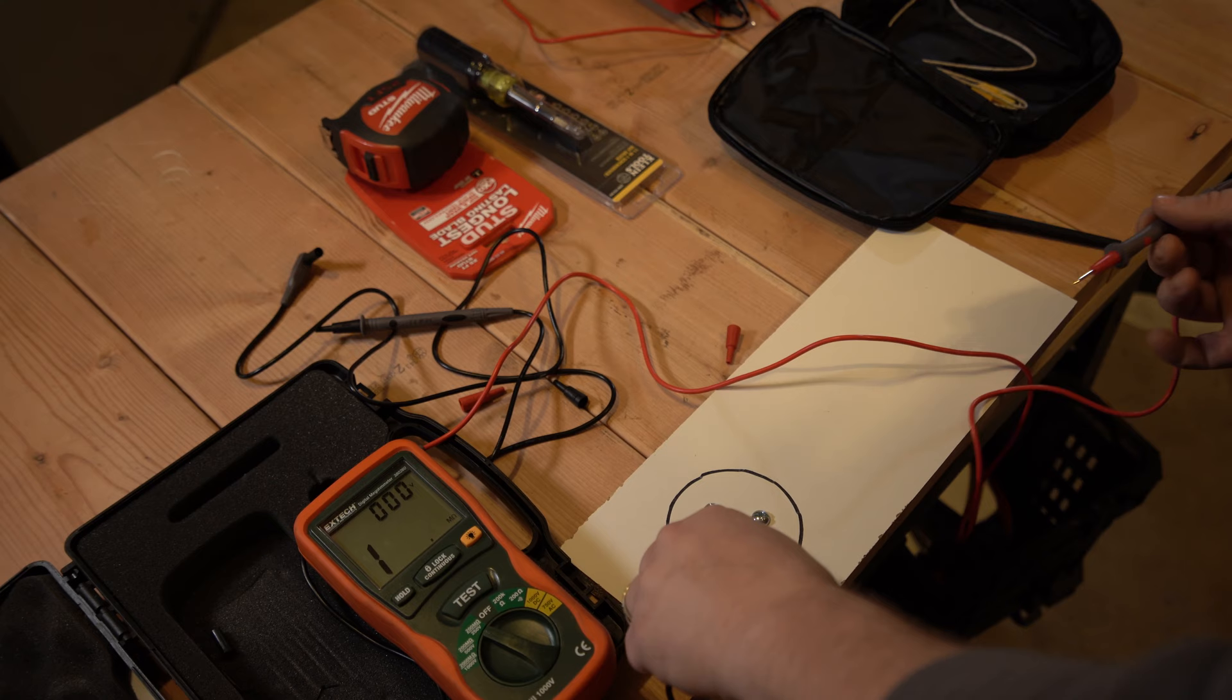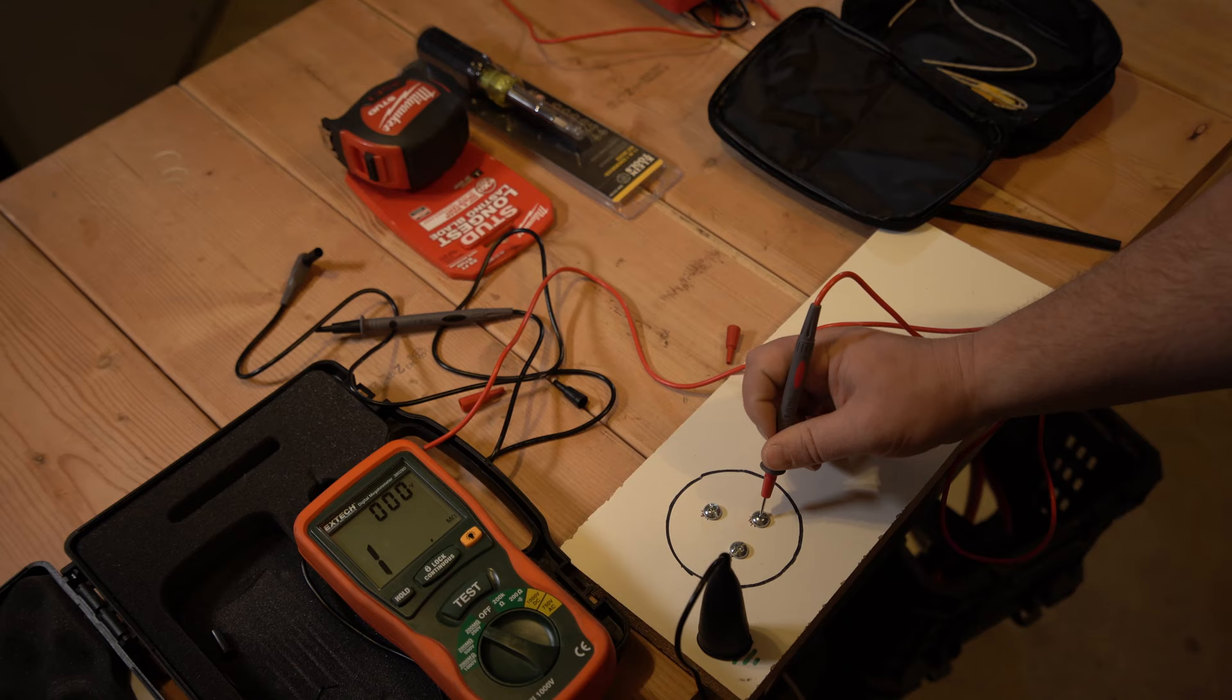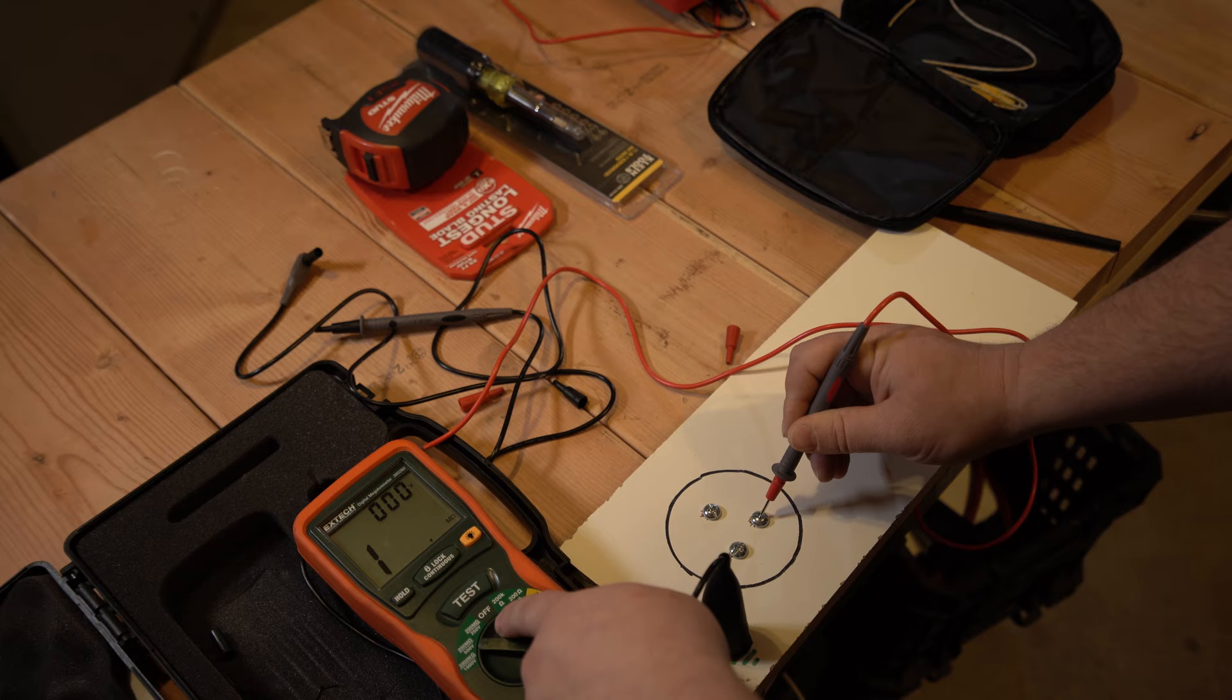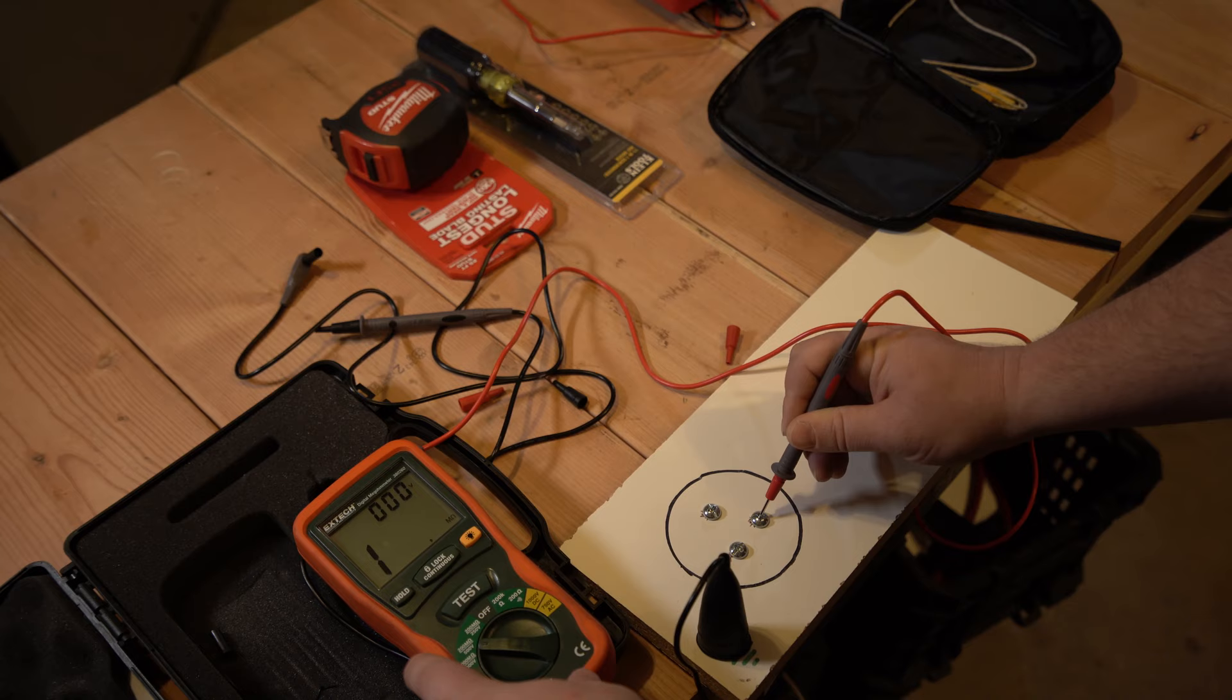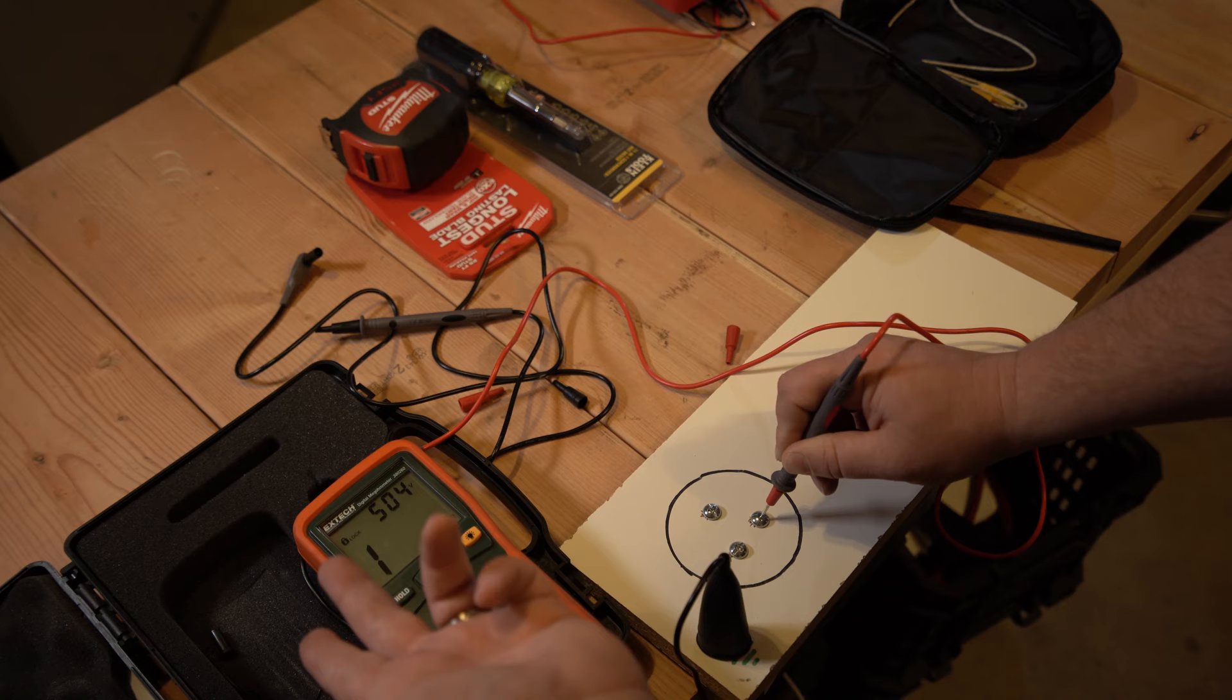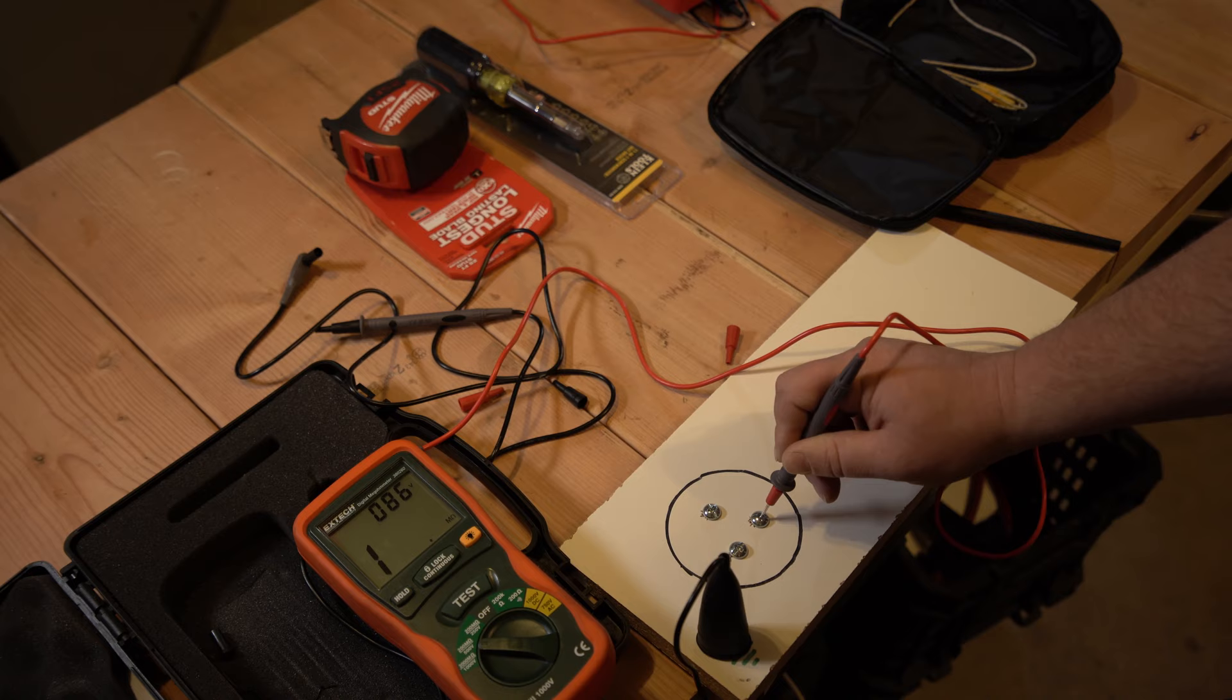After you verify that your meter runs properly, like I said, connect that to a good ground on the housing of the motor or the compressor and then you're going to start your test. Set everything up, take your meter lead to one of the windings, running at 500 volts. You can start at whatever, you can see that at 250 volts it'll read up to 200 megaohms, 500 volts still 200 megaohms, and at 1000 volts it can read up to 2000 megaohms. We're going to hit test, I hit lock, so you can see we're running 504 volts and we're reading nothing on this meter. The one over here is signifying that it's OL, you're not getting any reading through it. After you take the lock, you want to let your meter discharge the voltage all the way down to zero before you remove the lead. And you're good to go.